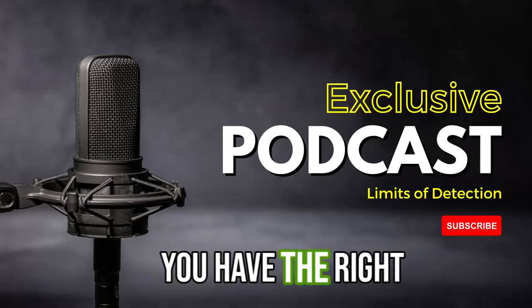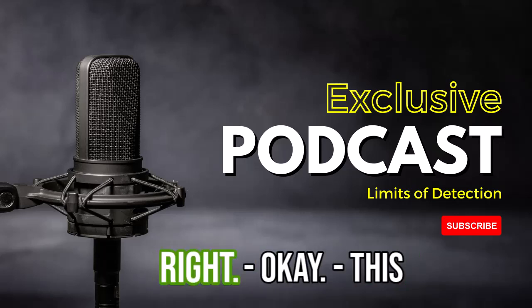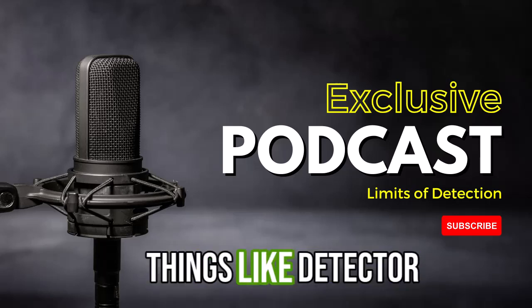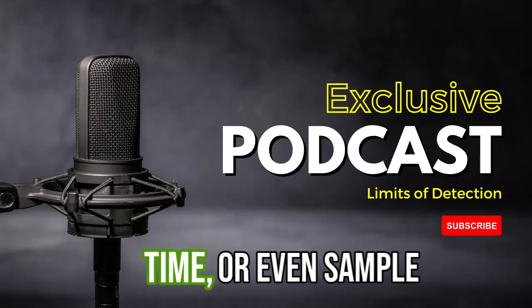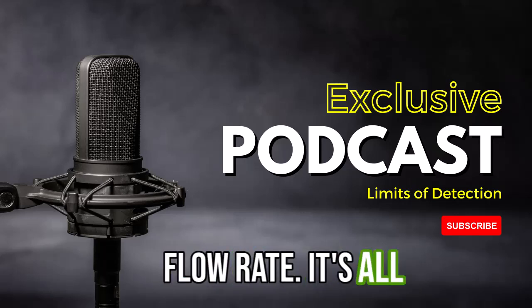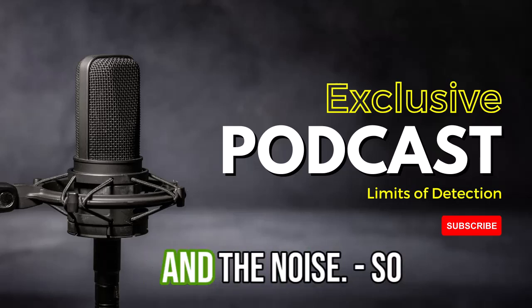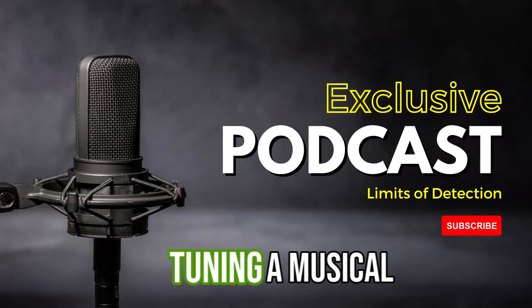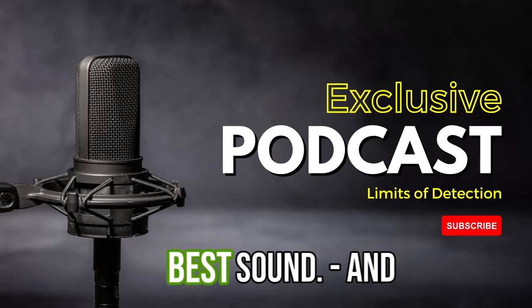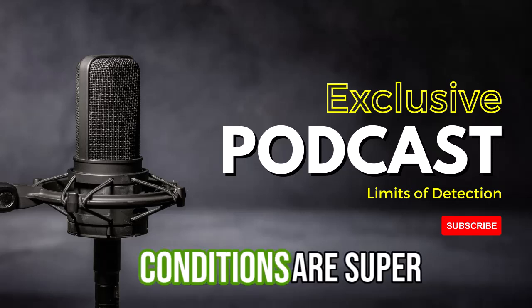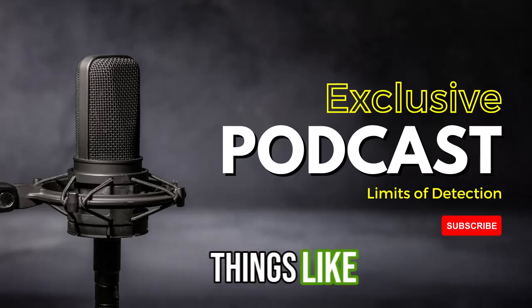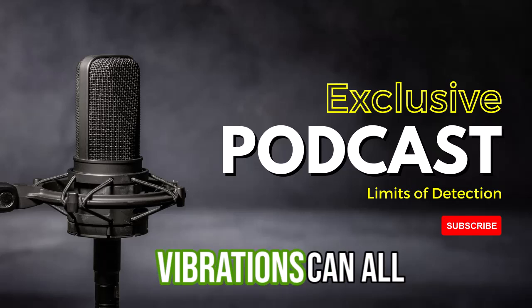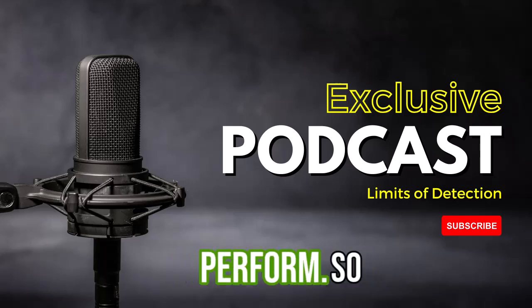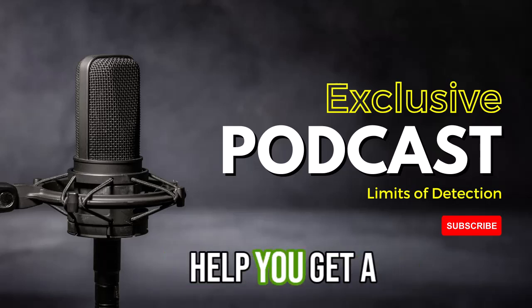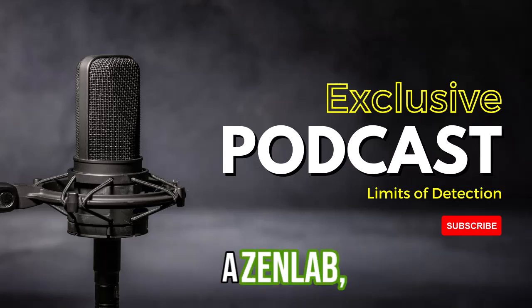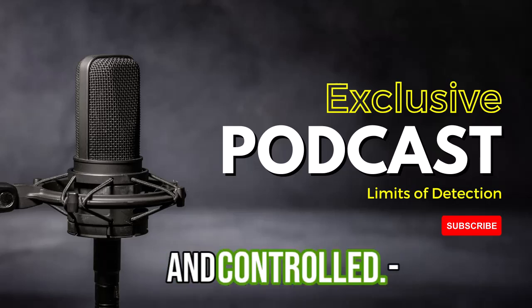Exactly. And once you have the right instrument, you need to make sure all the settings are right. This means adjusting things like detector gain, integration time, or even sample flow rate. It's all about making sure your signal is strong and the noise is low. So you're like fine-tuning a musical instrument. Yeah, exactly. To get the best sound. And environmental conditions are super important too. Things like temperature, humidity, and vibrations can all affect how your instruments perform. So maintaining a stable environment can help you get a better LOD. So like a Zen lab. Keep things calm and controlled.